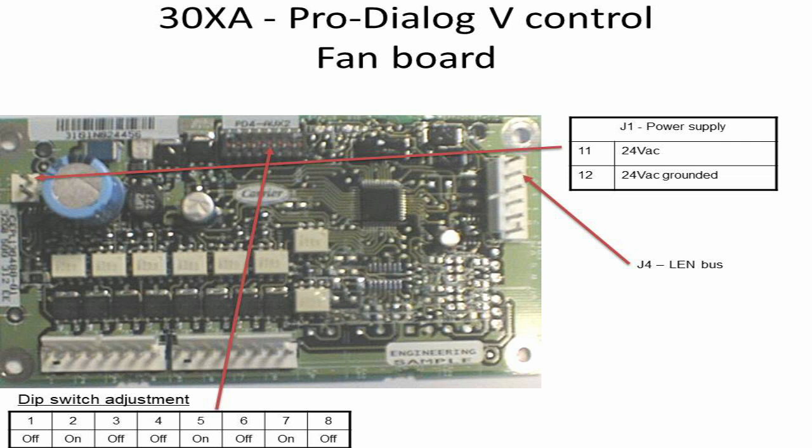Carrier 30XA Pro-Dialog V uses a fan board to control the number of fans required to run to maintain the discharge temperature in the chiller. The fan board receives a signal from the main base board to turn the fans on or off for a specific circuit. The main base board monitors the discharge pressure and sends commands accordingly to the fan board.